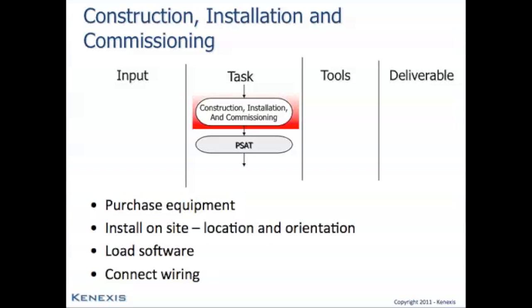Installation of the field equipment for fire and gas detection and suppression systems is also going to be very important, because the location and the orientation of the detector array have a very strong impact on the ability to achieve your tolerable risk targets. Thus, it is not enough to simply confirm that the device is in the field somewhere. It needs to be in the specific location that was specified. It needs to be at the specific orientation, meaning angle of rotation and angle of declination that was specified. Furthermore, you'll need to confirm the field of view of the detectors is consistent with what was assumed during the design phase. And if not, the coverage models need to be recalculated to confirm that coverage targets have still been achieved.